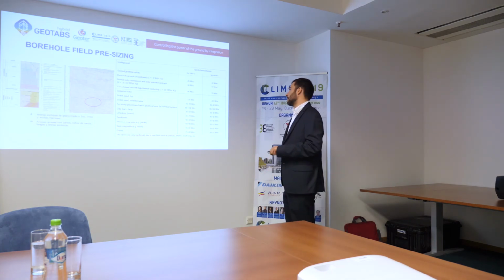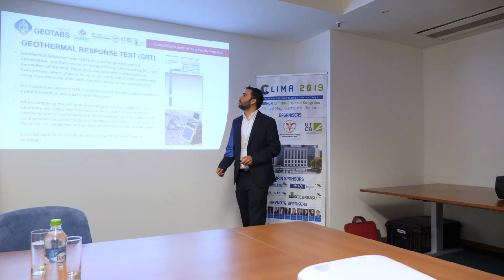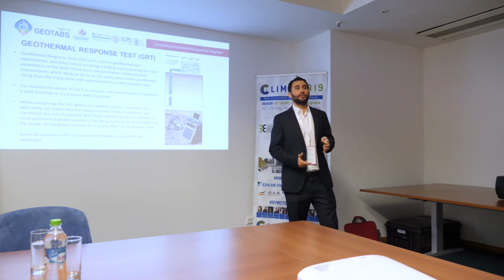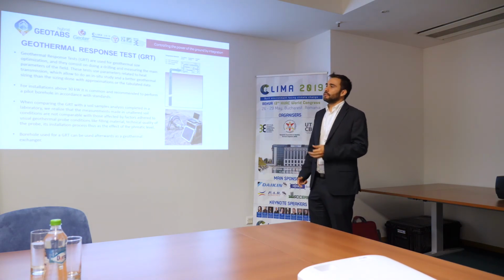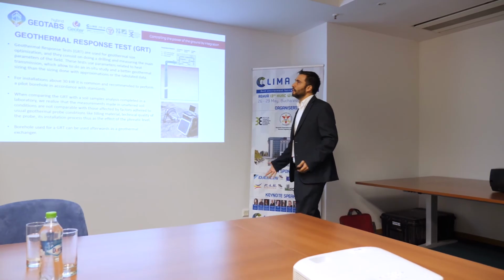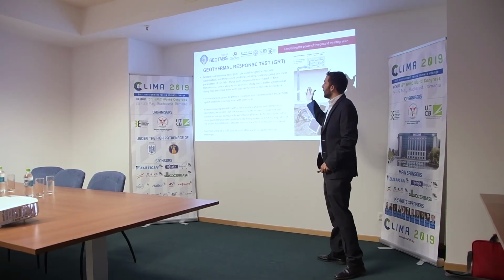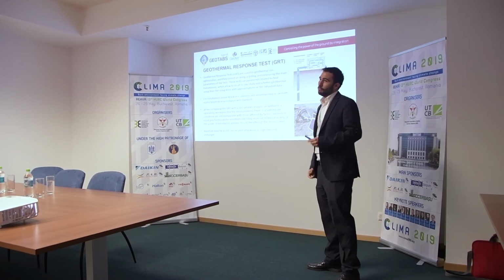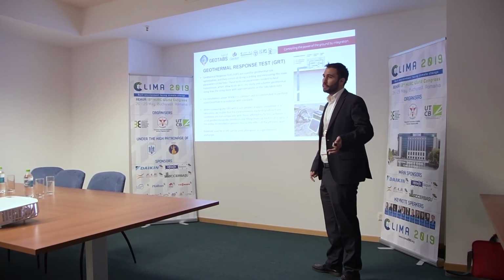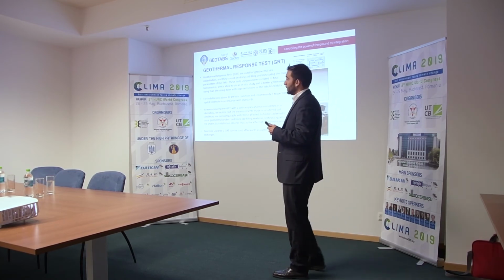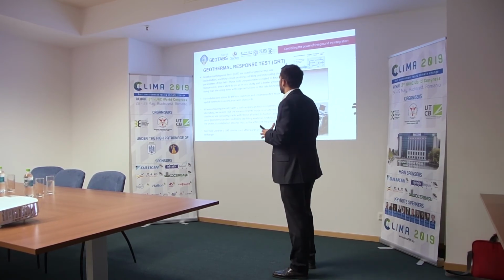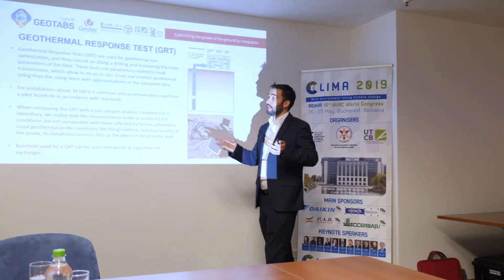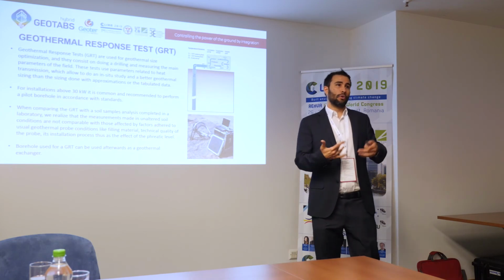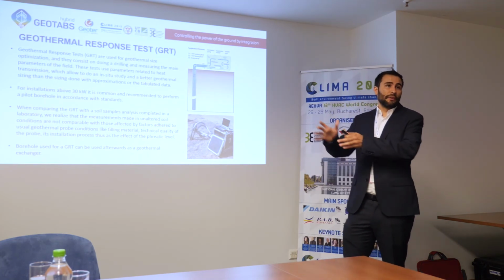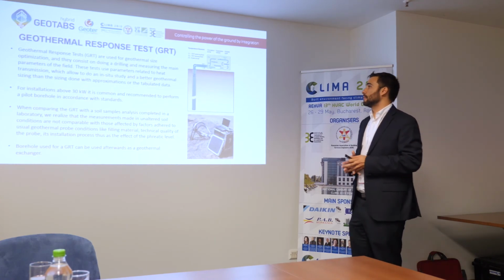But this is only for a very small installation, not for medium or big installations. When we have an installation of more than 30 kilowatts, it is completely recommended, even necessary, to do a geothermal response test. The geothermal response test is the most prevalent practice for the sizing of a heat exchanger. It consists of drilling one borehole, a pilot borehole. This pilot borehole is going to be part of the final installation, so it's important.